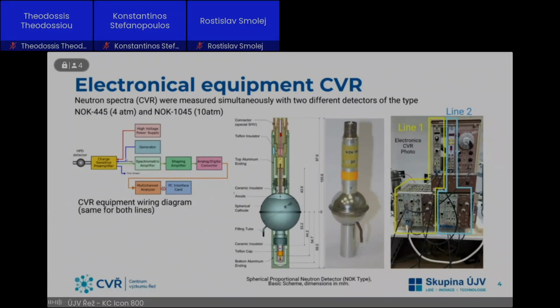Then the signal of the detectors comes to the charge-sensitive preamplifier. Of course, you have to accelerate the electrons or the ions by high voltage. The two different detectors operate with about 2,000 and 3,000 volts of bias high voltage, and then these signals go over the analog to digital converter, and you get a spectrum. On the right side, you see the equipment, which is based on NIM modules at the present time, and this is part of the infrastructure that was, let's say, lent to the Faculty of Nuclear Engineering.